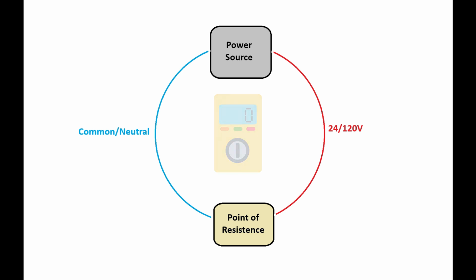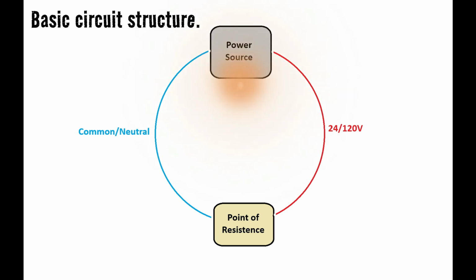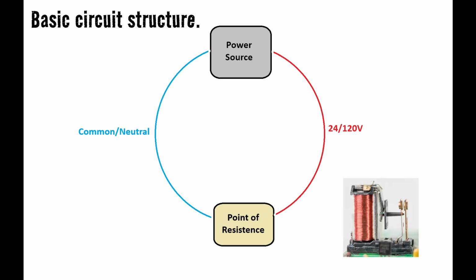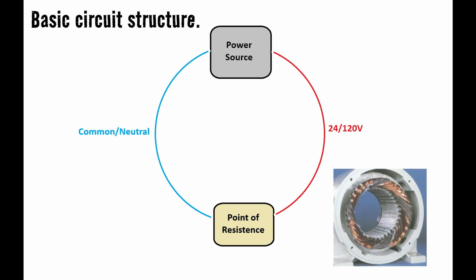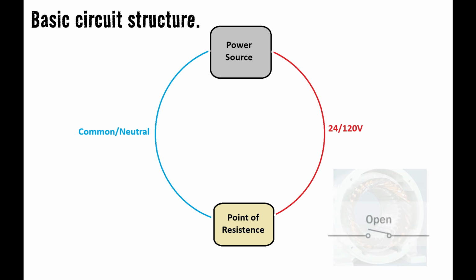What you're looking at here is a diagram I made of a basic circuit, right? So we have our power source, we have our hot wire, we have some point of resistance, which could be a coil in a contactor or a relay. It could be a winding in a motor. It could even be an open switch. And then on the other side, we have our common or neutral. That brings us back to our power source.